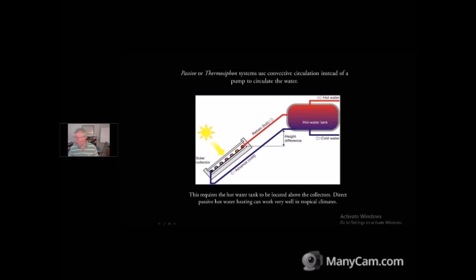Passive or thermosyphon systems are going to use convective circulation instead of a pump to circulate the water. You can see here in this diagram what you have to do is you're putting the hot water tank physically higher than the collector. The reason is you want the cooler water from the bottom of the hot water tank to go downhill, be pulled down by this convective current, and then to be heated up in the collector and then pushed back up as it expands into the hot water tank. That is a passive or thermosyphon system.